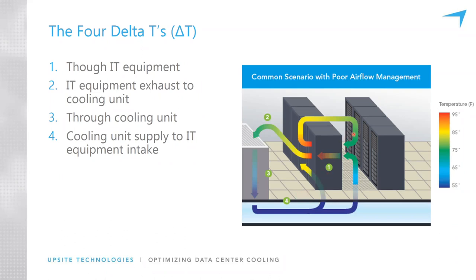To achieve a maximum intake temperature of 75 or 80 degrees, as most people do, requires in most environments, because of poor airflow management and poor optimization, a supply temperature from cooling units of 55, 60, maybe 65 degrees. That 60 degree air often warms up 20 degrees by the time it gets to the warmest intake temperature. So delta T4 is 20 degrees, a 20 degree increase in temperature from the time it leaves the cooling unit to the warmest intake. And the exhaust, we know the air coming out of servers is easily around 100 degrees. Then why is the return air temperature at the cooling units often around 70 degrees? Why is that delta T 30 degrees? Why is it 30 degrees colder from the time it left an exhaust to returning to the cooling unit?